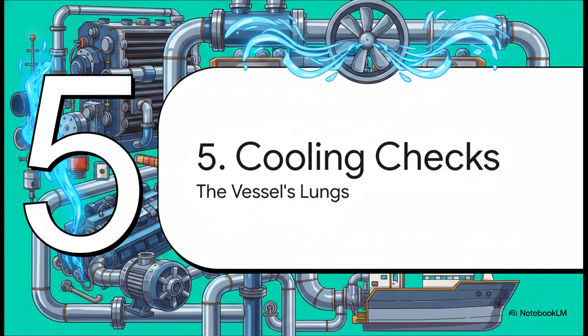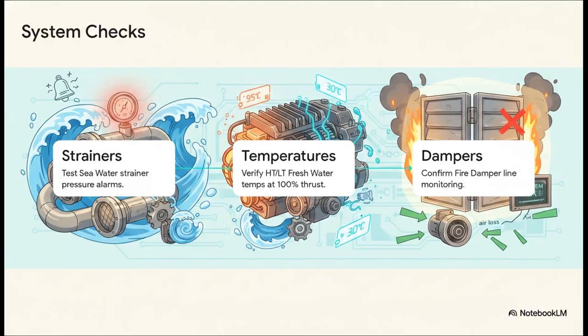Section 5. The lungs of the ship. Cooling and ventilation checks. Engines are completely useless if they can't breathe or stay cool. We follow these precise steps to check the engine cooling systems and pumps, making sure to confirm all emergency temperature and pressure sensors are working. We also run through instructions to verify the ventilation and fire dampers. It is absolutely crucial to confirm that engine room fire dampers fail exactly as set on air loss, rather than accidentally choking the oxygen supply to your running engines.